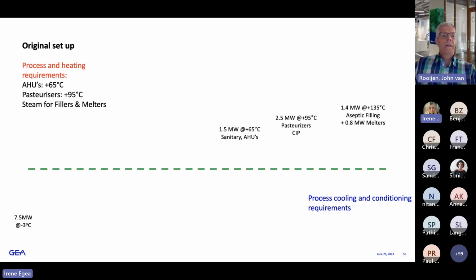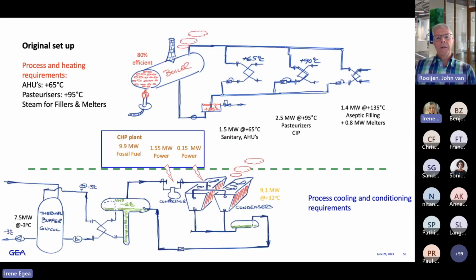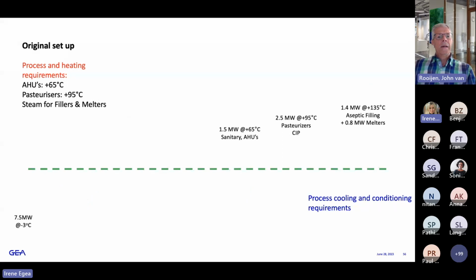If you look at the original setup, the demands for HVAC, air conditioning, offices and sanitary were a demand for 65 degrees water at about 1.5 megawatt. For the pasteurizers and CIP, there was a demand of 2.5 megawatt of heat at a temperature level of 95 degrees. On steam level, there was a demand of 1.4 megawatt for aseptic filling of the bottles, and also 0.8 megawatt for melting the concentrated product. On the cooling side, there was a demand of about 7.5 megawatt at -3.